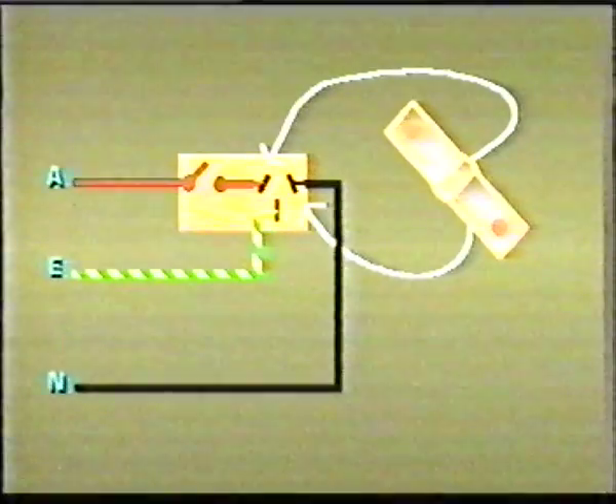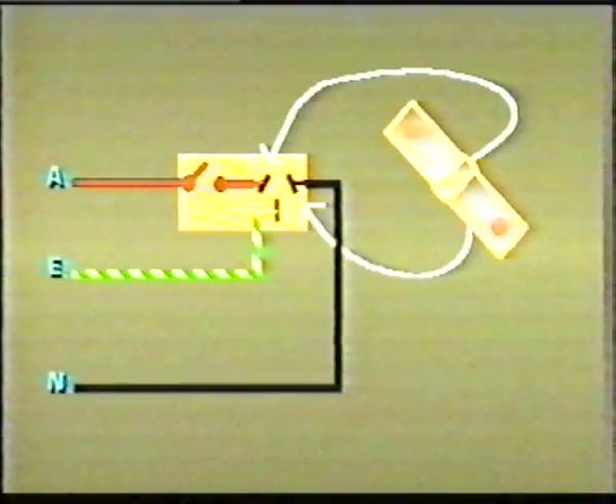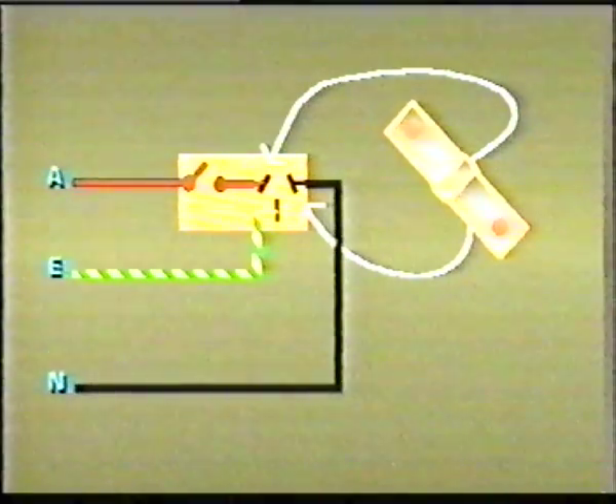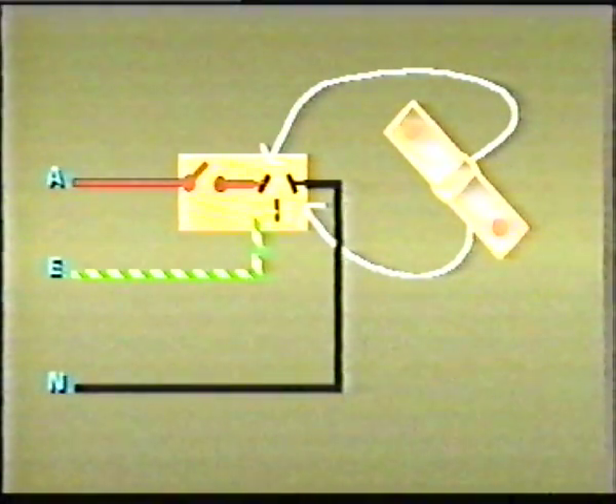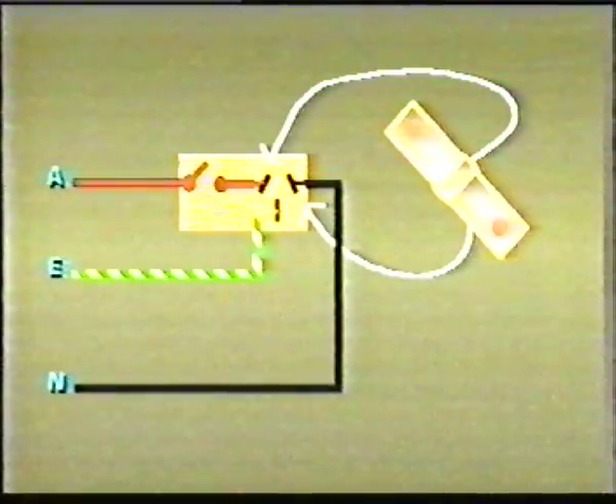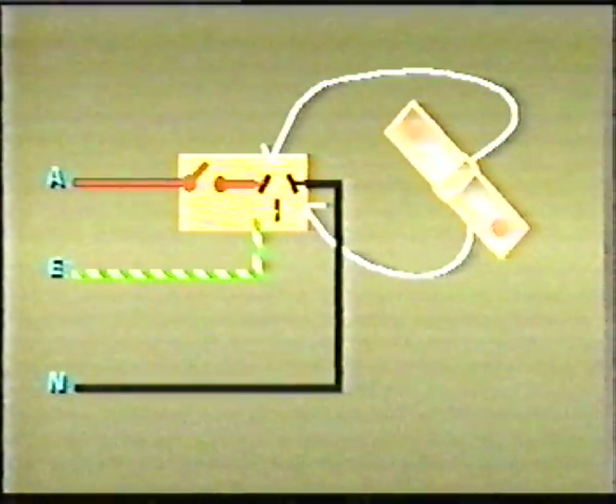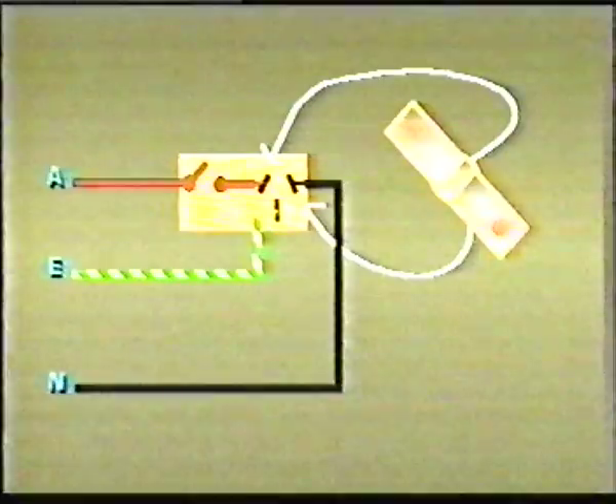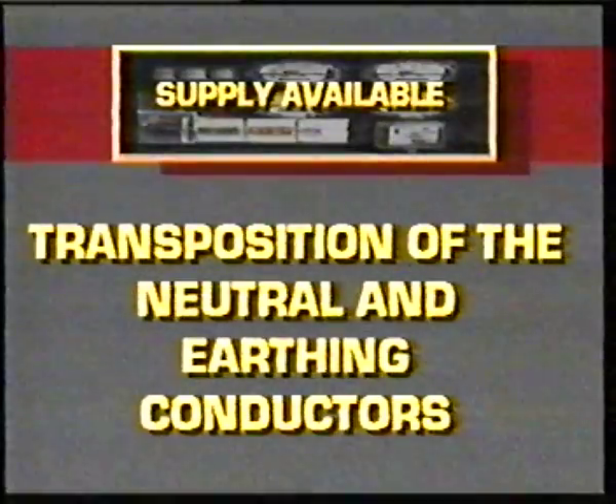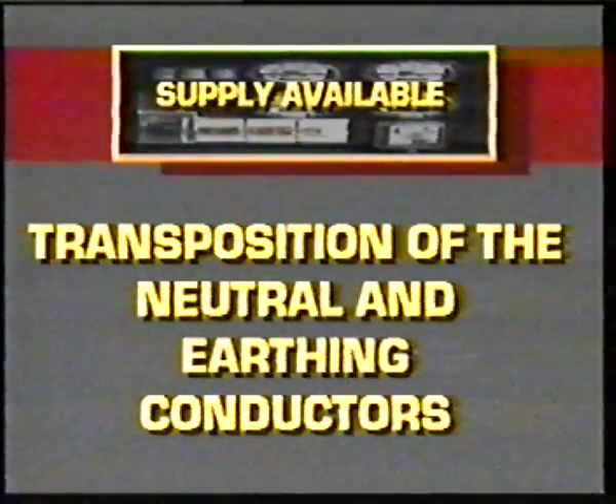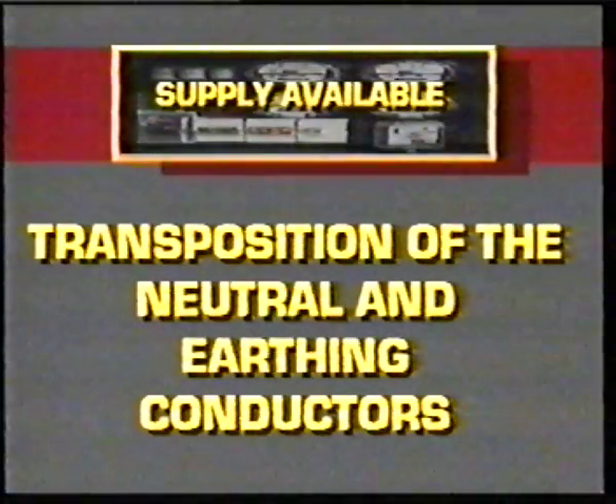Correct polarity is indicated when the switch is on if there's a normal glow between active and neutral and active and earth, with no glow between neutral and earth. When the switch is off, there should be no glow between active and neutral, active and earth, or neutral and earth.